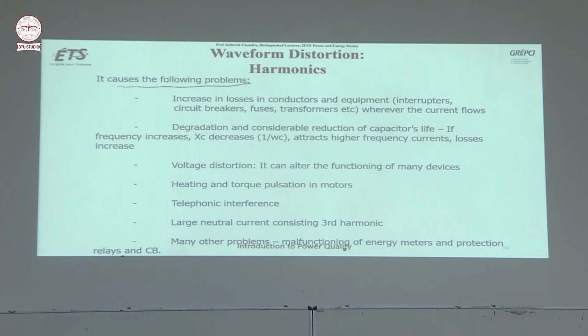It may cause the following problem: increase in losses in conductors and equipment, fuses, transformer, wherever the current flows. Why will the losses increase? First thing is the ohmic losses. And then perhaps you might have studied skin effect. Suppose this is the conductor. If frequency increases, then the current will remain near the surface. Most of the current will remain near the surface of the conductor. So this is what is called skin effect. Because of that, the resistance increases, so losses will increase.